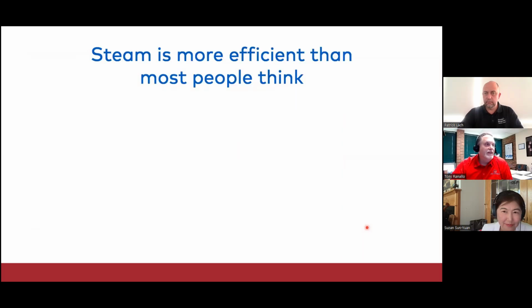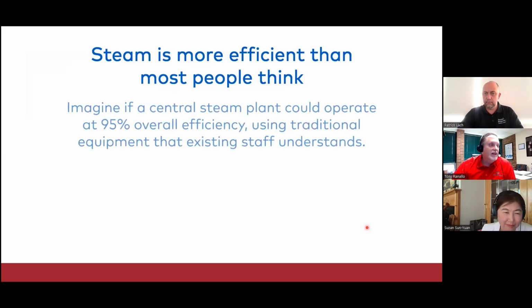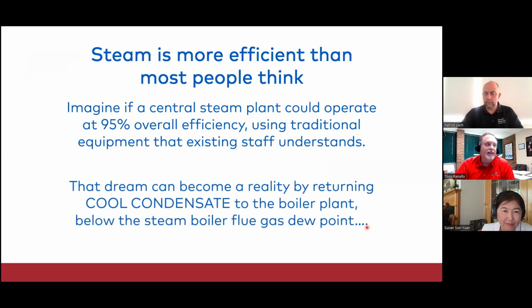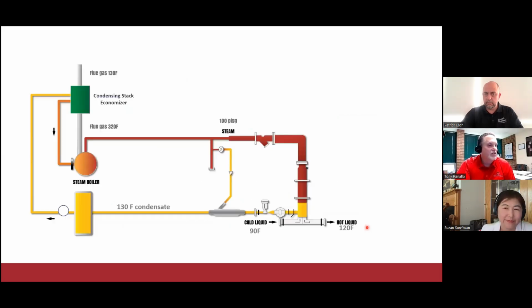So, is steam more efficient than most people think? We believe so. Try to imagine a central steam plant that could operate at 95% overall efficiency using traditional equipment that existing staff understands. That dream is a reality by returning cool condensate to the boiler plant below the steam boiler flue gas dew point. Now, we're going to get into more detail of that in a few slides, so just hang on to that thought for a minute.